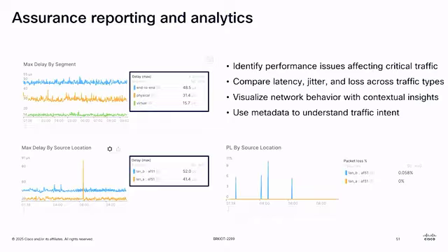Yeah, that's about it. This is an interesting example of some things that are not visible. This hasn't failed. You have dual paths. Your PLCs are still running. But if for some reason your LAN B is not behaving correctly, it has some loss, and you lose LAN A, you are not really protected. So having this data and being able to monitor this data will allow you to take actions to fix LAN B before it becomes a problem. Good point. Thanks, Erica.